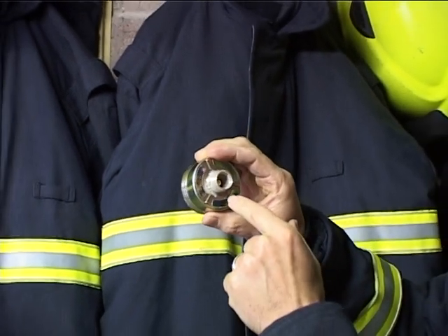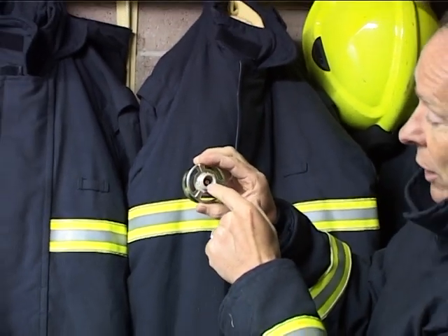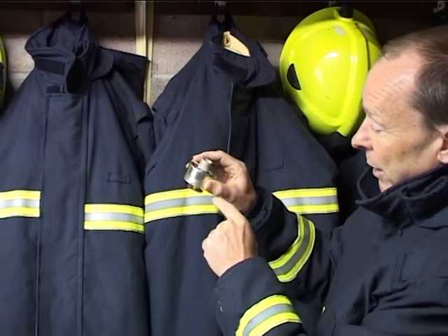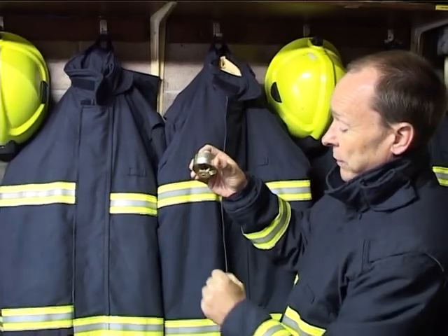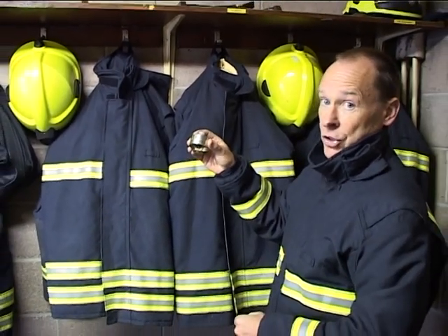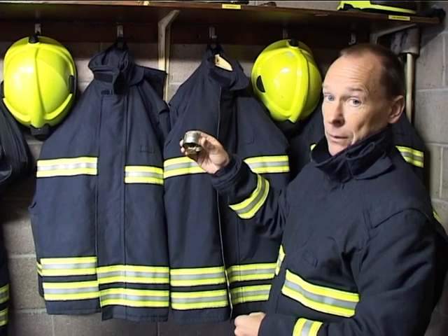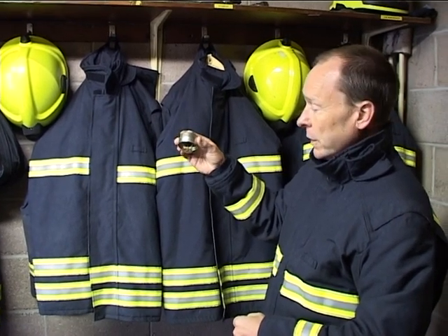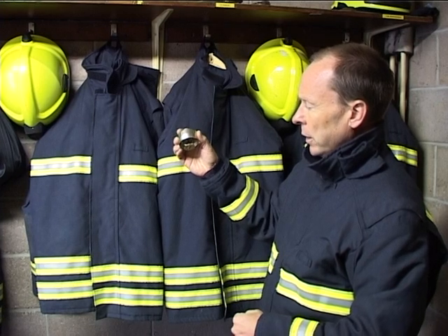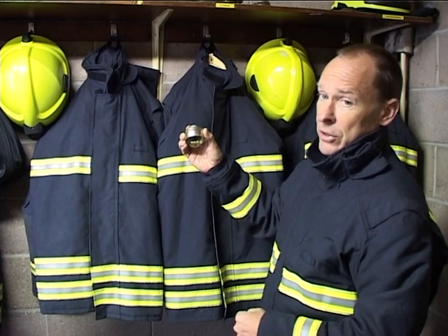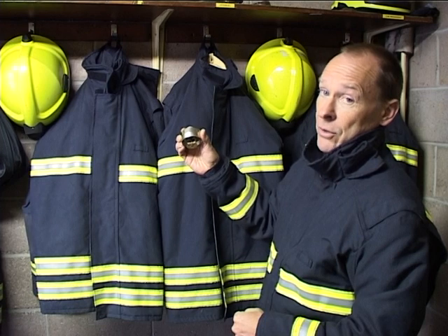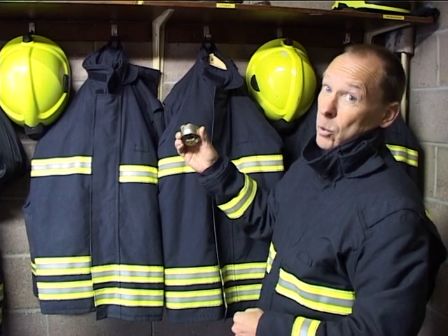When it breaks, that allows the water pressure to push out a little brass cap, allowing the water to then hit the deflector plate and create the cone shape, which is typical of a sprinkler system. And that's what will control the fire. As I said, these are incredibly reliable. And worldwide statistics have shown that for every 16 million heads that are manufactured, only one will malfunction.